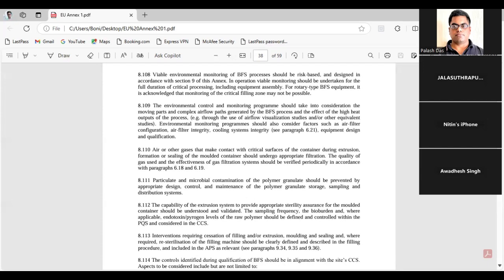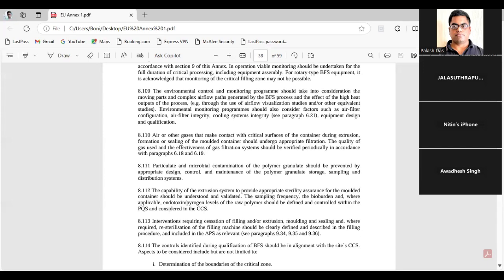In regular operation, they are not changing the plate. The plate remains the same. The timing they are changing, like 200 liters, then after 30 minutes 200 liters, then after 30 minutes 200 liters. In this manner they are doing it, not disturbing the air sampling plate. The air sampler has that provision, where pulsation time can be fixed, and that they qualified. I was just thinking whether extra samples are being taken, like more than 1,000 liters, so this may be possible.